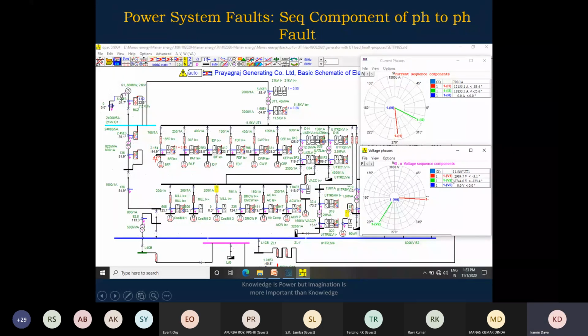Similarly, the positive sequence voltage is 2.9 kV. The negative sequence voltage is 2.7 kV, and zero sequence voltage is 0. So this is how you look at it here in a voltage and current bars. The phasor value of voltage is 2.8 kV A phase, 2.88 kV B phase, 5.72 kV C phase. Current is 20.99 kiloampere A phase, 20.54 kiloampere B phase, and 543 ampere C phase.